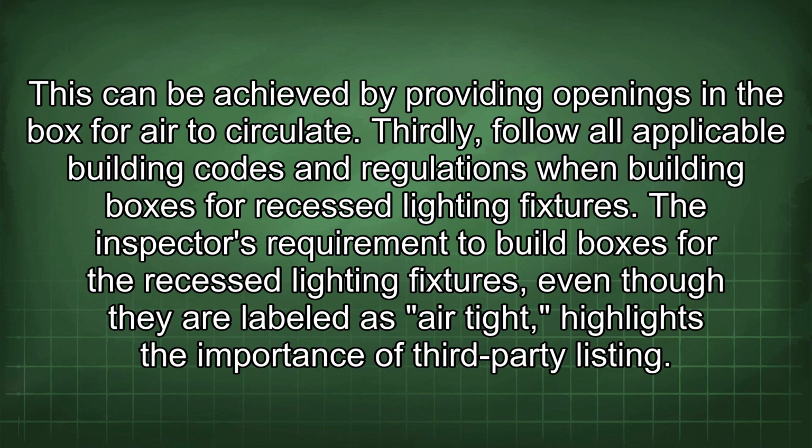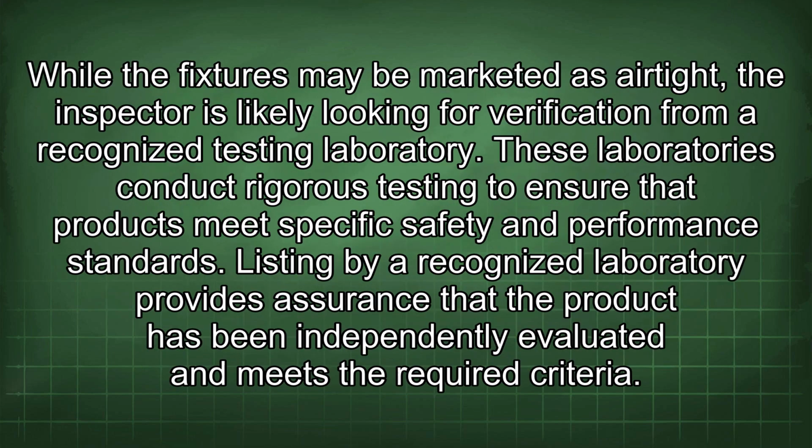The inspector's requirement to build boxes for the recessed lighting fixtures, even though they are labeled as airtight, highlights the importance of third-party listing. While the fixtures may be marketed as airtight, the inspector is likely looking for verification from a recognized testing laboratory. These laboratories conduct rigorous testing to ensure that products meet specific safety and performance standards. Listing by a recognized laboratory provides assurance that the product has been independently evaluated and meets the required criteria.